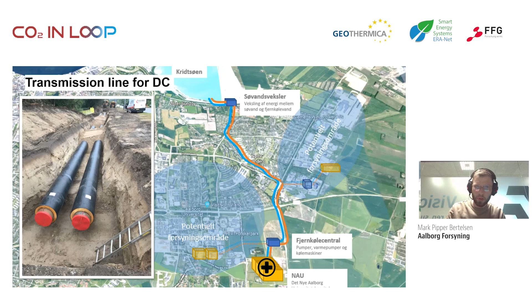We also have a district cooling central at IKEA. This is a smaller, more decentralized district cooling plant where we have 1 megawatt of cooling installed in heat pumps, which can also provide 1.4 megawatts of heating. We send in 8 degree cooled water to IKEA, and they return it at 13 degrees.